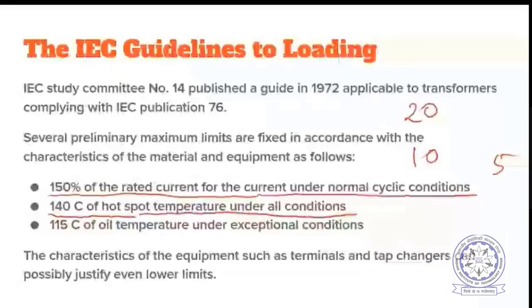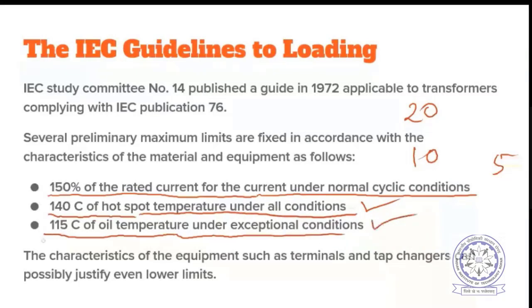Therefore, the IEC guidelines have decided that the hotspot temperature should never be allowed to cross 140 degrees centigrade. And for oil temperature also, there is a specification that, even under exceptional conditions, it should not be allowed to exceed 115 degrees centigrade.